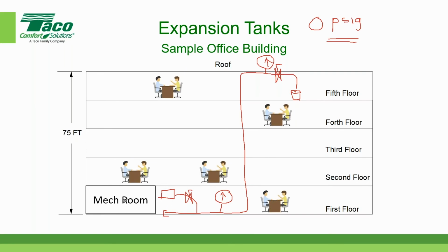Yes, so the pressure at the bottom is simply the height of the building converted into pounds per square inch. And the conversion factor is 2.31 feet per PSI. As someone just indicated, if the pressure is 75 feet of water column, I would divide that 75 by 2.31, and the pressure at the gauge at the bottom would read approximately 32.5, and that's correct. 32.5 PSI. The more precise number is 32.46, but I'm rounding it off to 32.5.